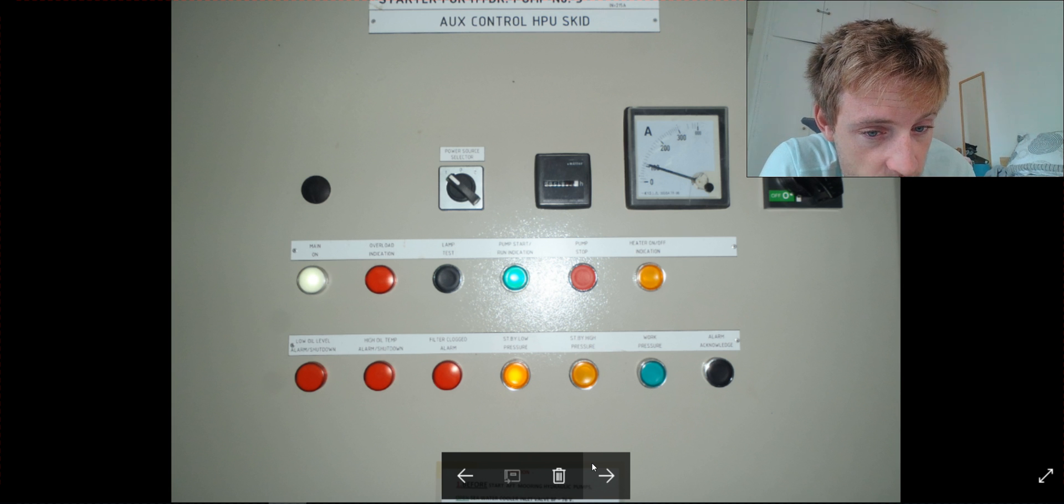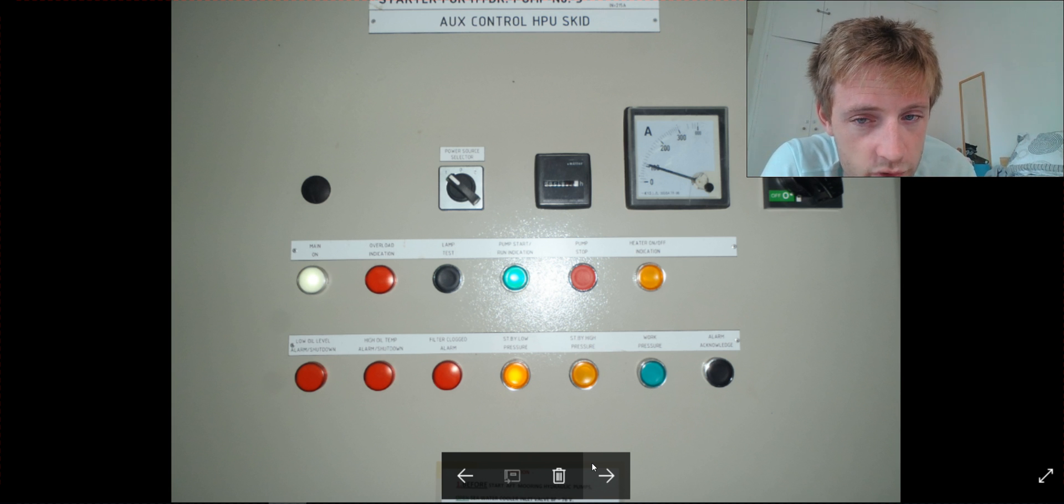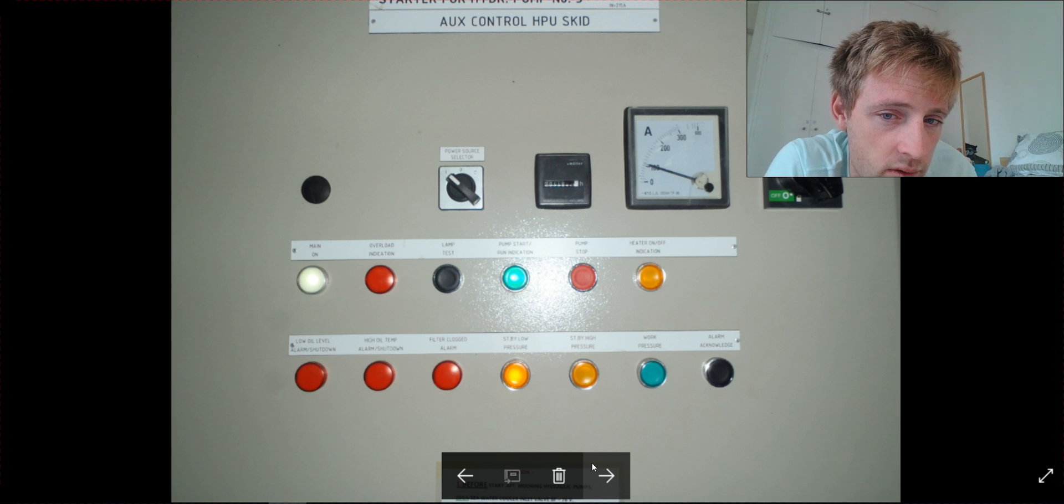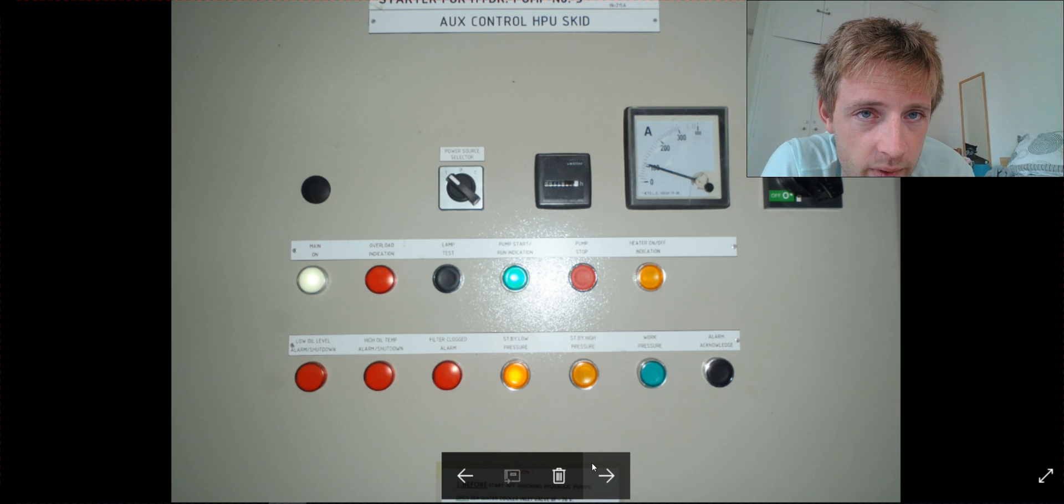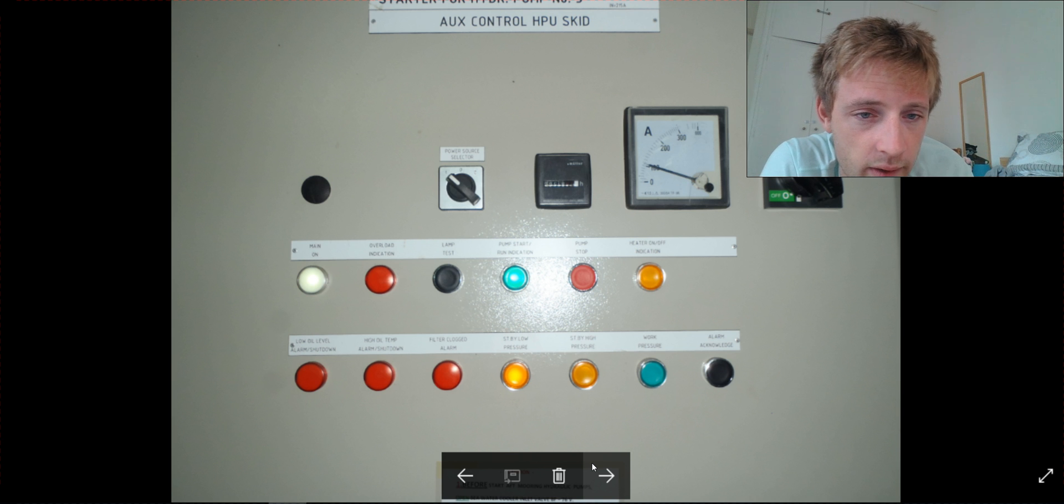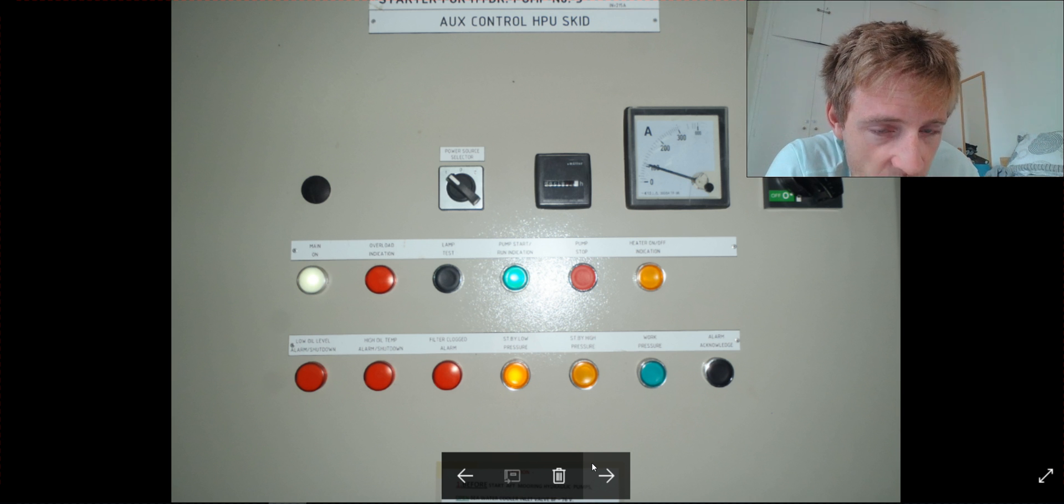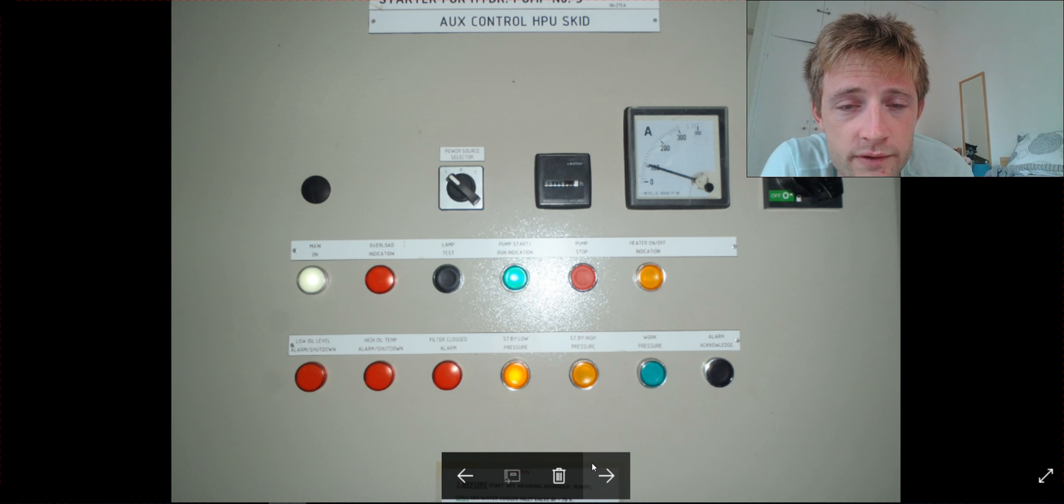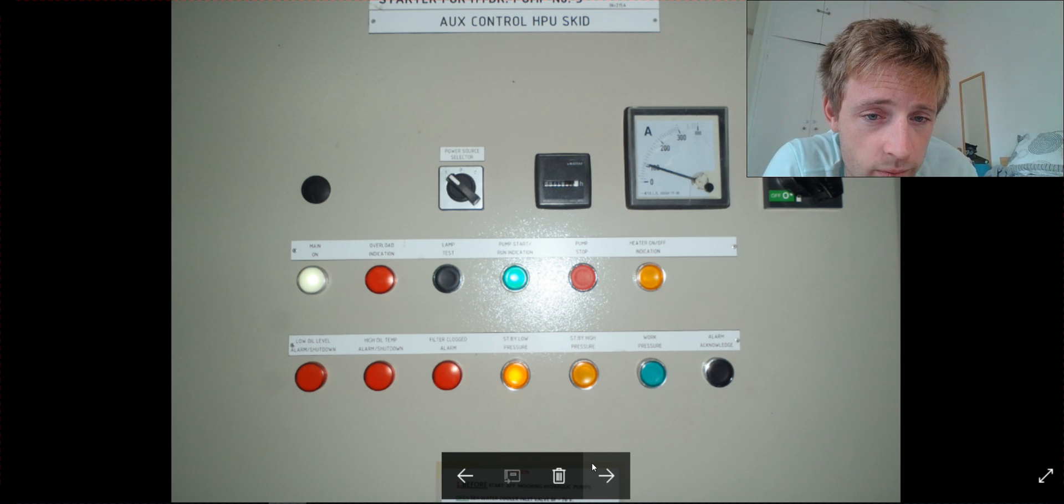On the low standby, on the high, and on work pressure. This is very important because if some motor has a problem, the amperage will be either lower or higher. Next, you will observe any leakages of hydraulic system.